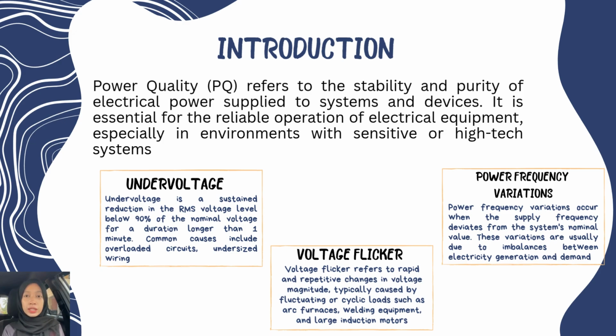Voltage flicker refers to rapid and repetitive changes in voltage magnitude, typically caused by fluctuating or cyclic loads such as arc furnaces, welding equipment, and large induction motors. These fluctuations usually range from 0.1 to 7 Hz and result in visible flickering of lighting, especially in incandescent lamps. Although not typically damaging to equipment, voltage flicker can cause discomfort, reduce workplace productivity, and generate customer complaints.